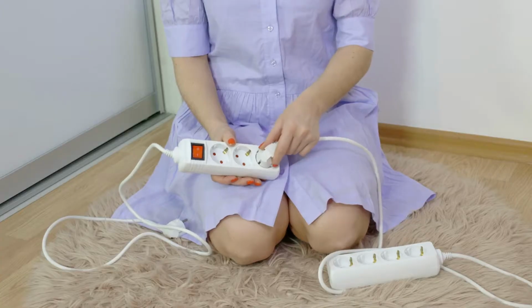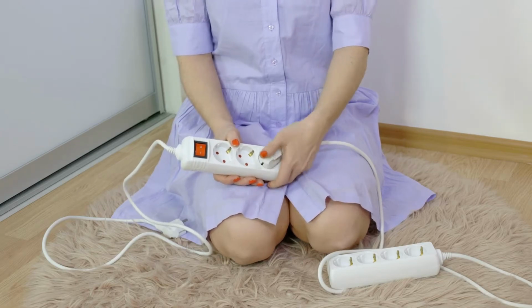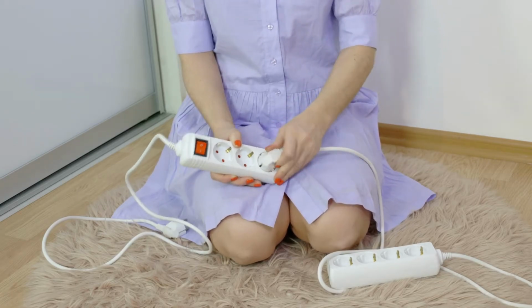And then you want to make sure that none of these extension cords that you're using are daisy chained, what we call daisy chained. That's when an extension cord is plugged into another extension cord or another device. So like a surge protector plugged into an extension cord, plugged into another surge protector. That's what we call daisy chaining. And we don't want to have any of that because those devices are not rated to be chained together like that. So we want to make sure it's just one device, one cord or one device to whatever you're powering.